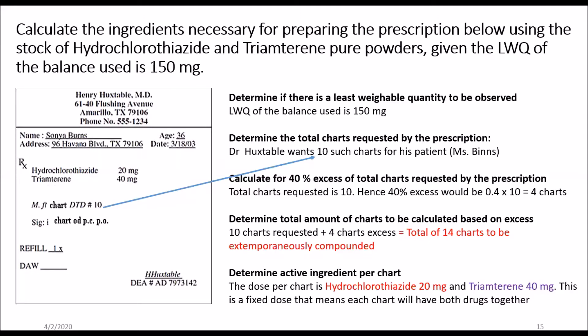Many times your electronic balance will tell you what the sensitivity requirement is. Depending on the sensitivity of weighing you would like in your establishment — if you want to accept an error of 10%, then your least weighable quantity will reflect that. Generally speaking, for compounding, an error is going to be plus or minus 5%, meaning we are 95% sure that what we are weighing is correct.